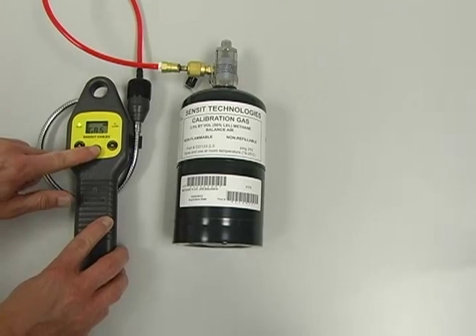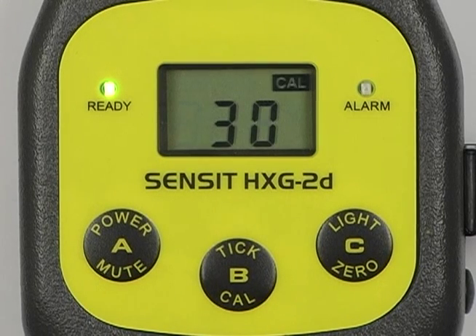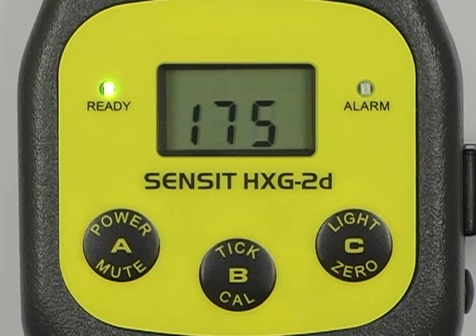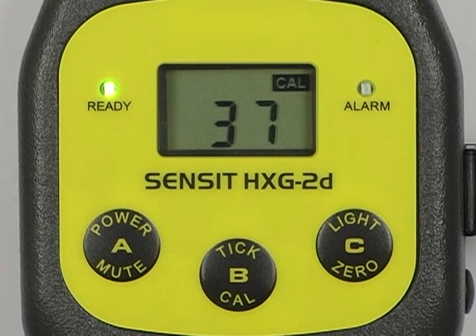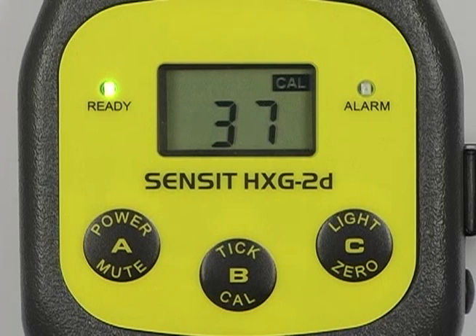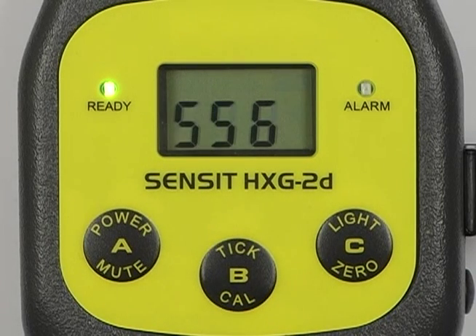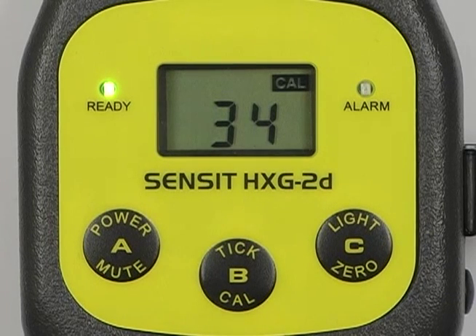Now place the black cupule on the end of the gooseneck assembly. Now press the B button again to start the calibration. During calibration, the numbers displayed on the screen are A to D outputs from the sensor going into the microprocessor. A successful calibration will be indicated by a beep followed by the CAL readings on the display.